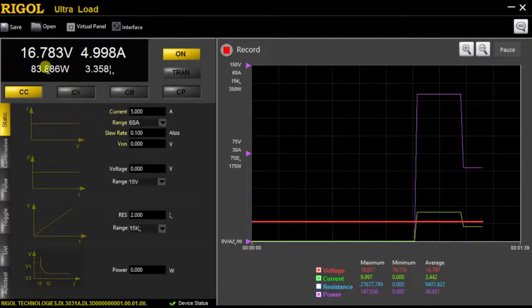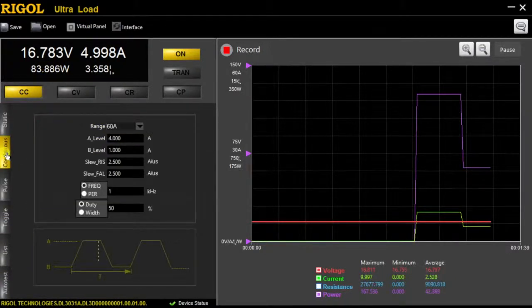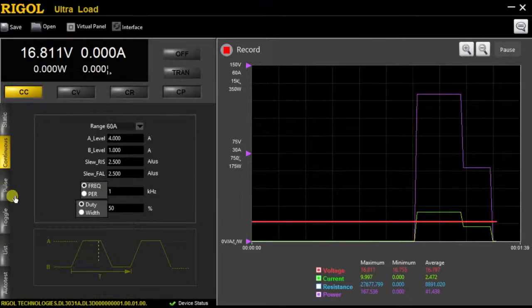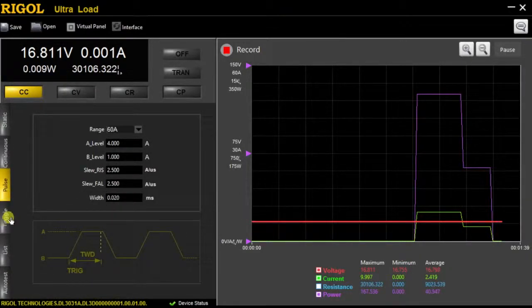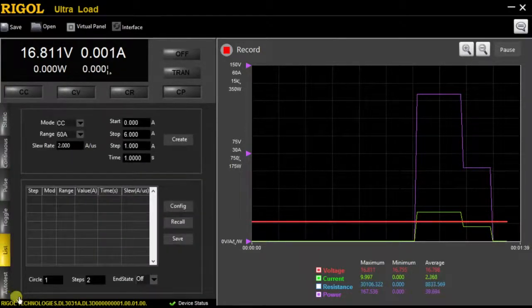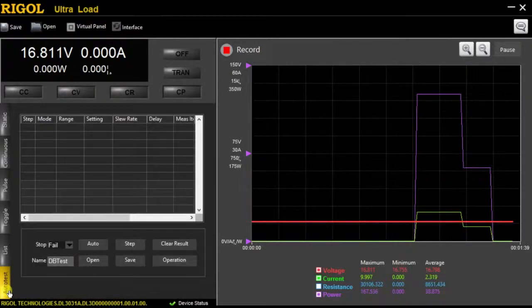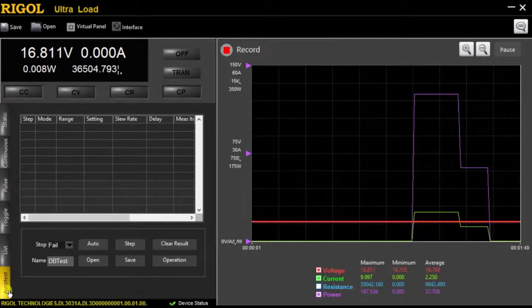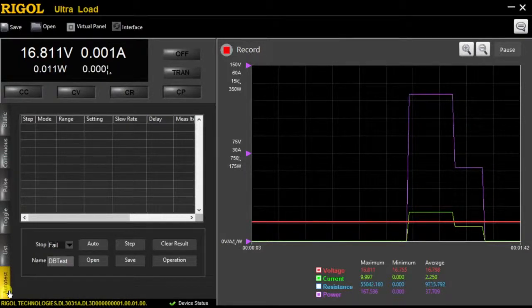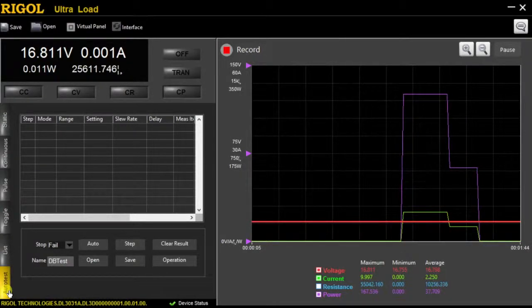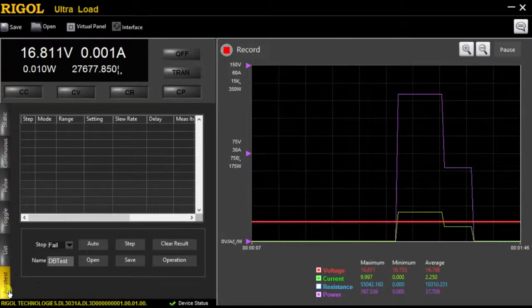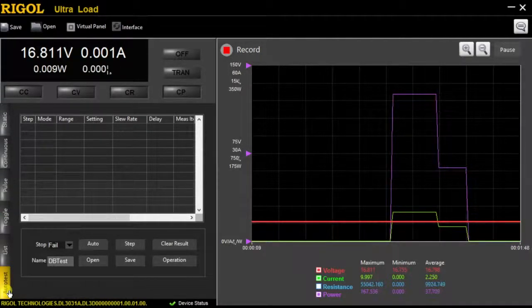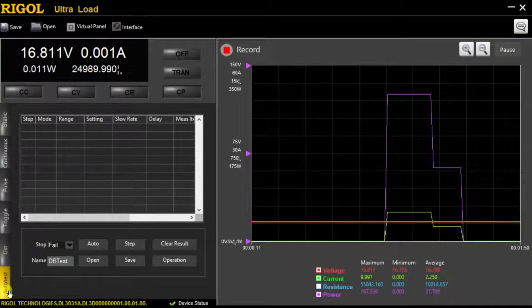Next, the four transient states. We can choose between continuous, pulse, toggle, list, and then we also have an auto test feature. To automate testing, say you wanted to do some battery testing overnight, you can set this up, set your different thresholds you wanted to step through. Either if you wanted to do just a constant power drain or more or less alternating power, you could totally set it up to do it.